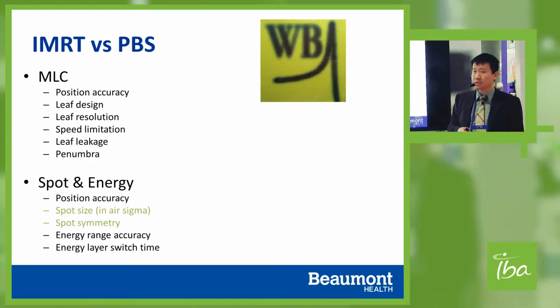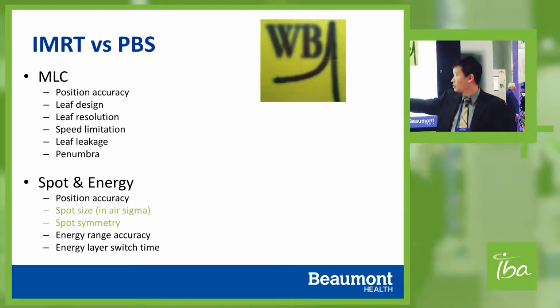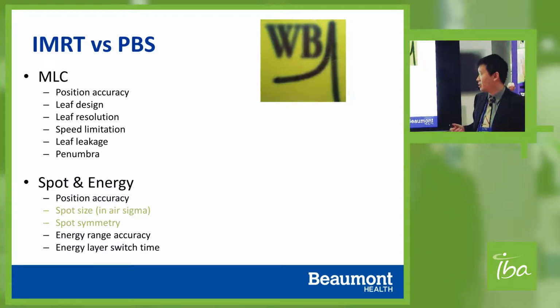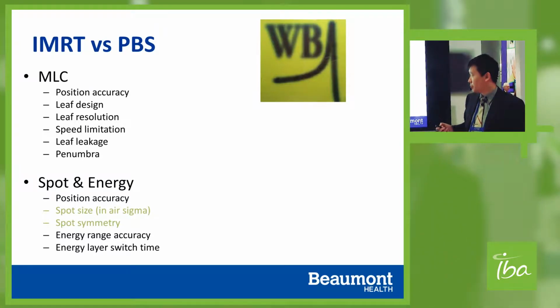So if we compare the photon commissioning and the proton commissioning, there are two major components. In photon, you have MLC, where positioning, leaf design, and the limitation of the speed play a key factor in your modulation capabilities, whereas for proton spot scanning, your spot shape, size, positioning, and energy accuracy determine whether you're able to draw such a nice picture or not.